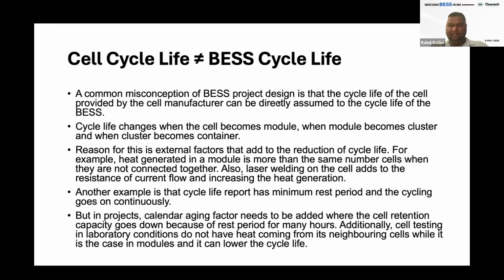And then again, there's a discharge at 0.5 C, and then again, there's a rest, and this continues. So as I was explaining before, calendar aging is where the battery degrades by itself during non-usage conditions. So that does not apply here. And calendar aging takes away a good chunk of state of health of a BESS during the project duration, or the project lifetime, yeah. So at a cell level, the temperature is pretty much 25. There is no calendar aging, and there's a good rest period, which again in projects may not be the case.